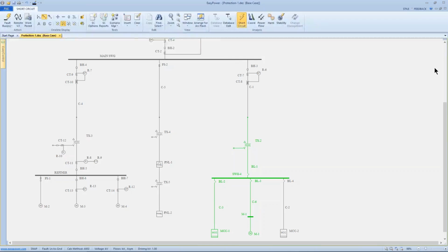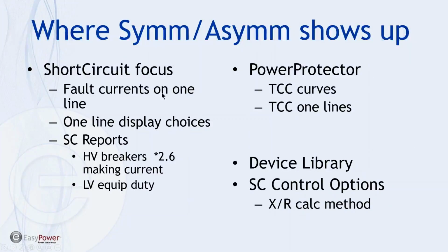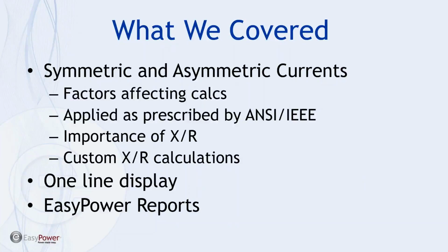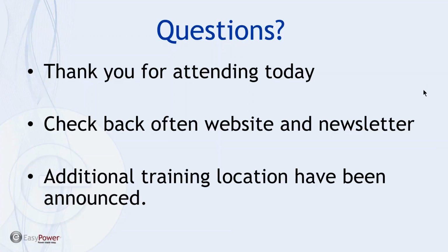Okay, I think that covers most of what I was trying to deal with here on our agenda. Basically, we discussed symmetric and asymmetric currents, the factors affecting how they're calculated and extracted from the one line, how they're being applied per the ANSI IEEE standards, and how important X over R is, and conversely or inversely, how important the values of the utility interface are, because that's the reference point that we have for all of these calculations. And we showed how the one line displays and the symmetrical and asymmetrical values are displayed in the reports. So let me see if we've got questions now that we can address.